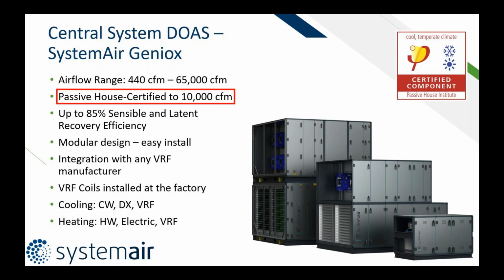Somebody said, "Are you going to send this presentation?" This will be available on our website, just so you know. And the in-unit ERVs can be mounted in multiple orientations. Yes. Okay, so like I said, this unit can be up to 85% sensible and latent recovery efficiency. Now, that's understanding that the wheel module actually can be oversized to the housing itself. So the housing could still be a size 27 housing with an oversized wheel. Just the wheel module would kind of extend beyond the unit itself. Now, typically, a typical selection would be a little bit higher than 80% sensible and latent recovery.